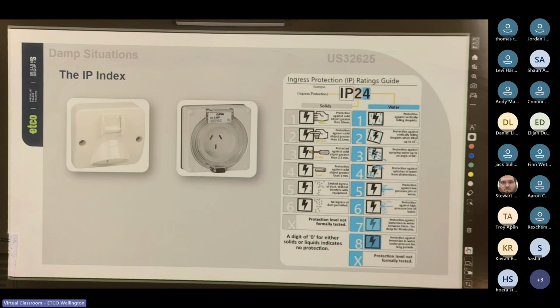Cool, so the IP index. This socket is usually used outdoors and it's IP53. So it's dust protected and protected against water drips up to 60 degrees from vertical. So it is normally installed outside. This is commonly your outdoor power point for your garden lights, for your power tools. It's not good practice, but some people install these for their outdoor infinity. Can anyone tell me why this might be a bad idea for your outdoor infinity?